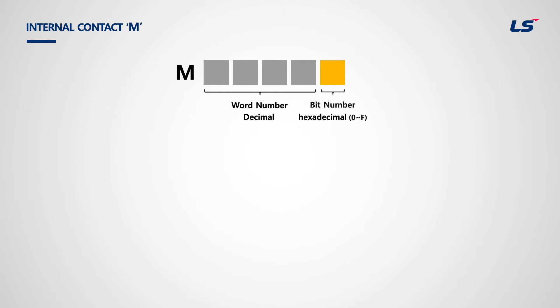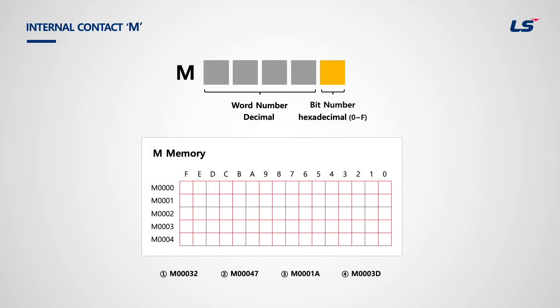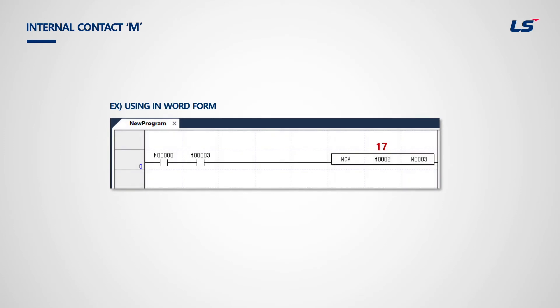Next is internal contact M. M and P are very similar; the only difference is that M is internal. For example, M32 is bit number 2 of word M3. When M0 and M3 are on, M2 is moved to M3. Note that A contact M3 has four zeros while M3 in the move function has three zeros. The move function requires word data while only bit can be used in contact. In this example, decimal value 17 is moved from M2 word to M3 word.